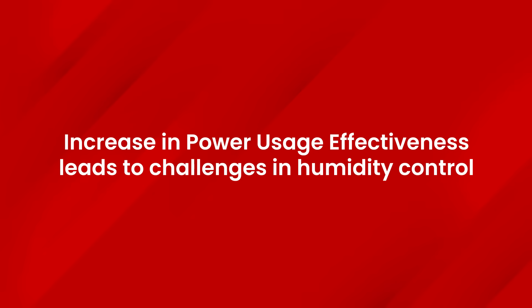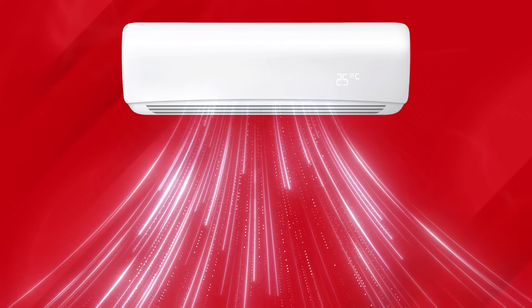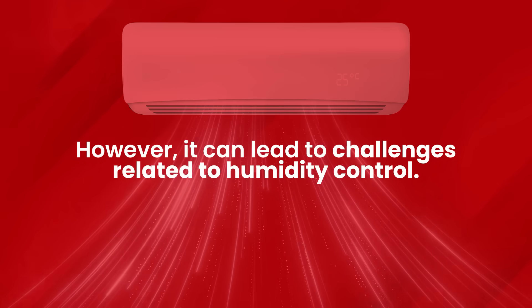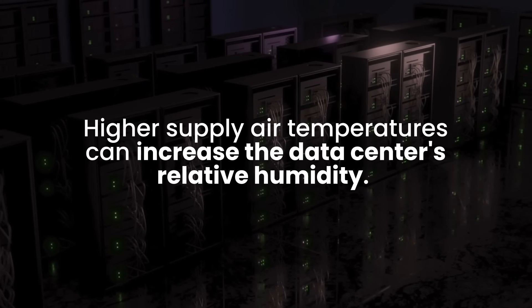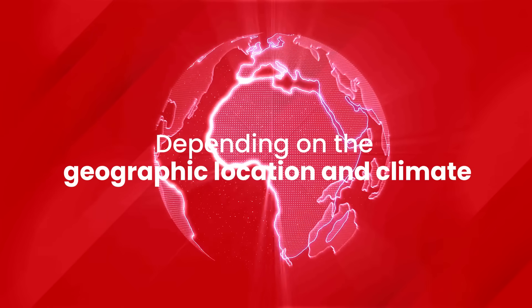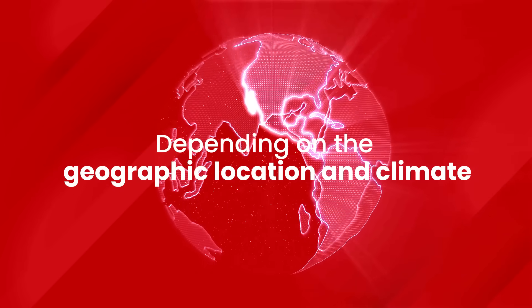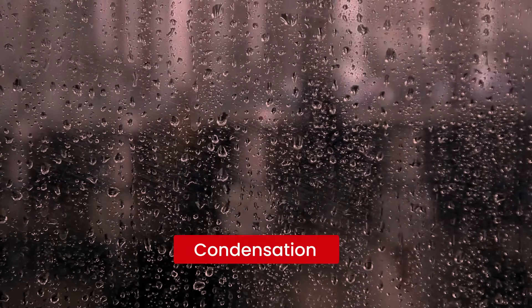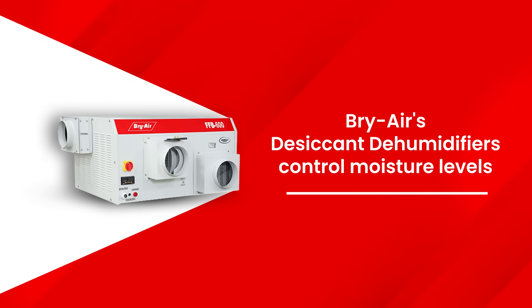To improve power usage effectiveness, data centers have been increasing the supply air temperature. This reduces the need for energy-intensive cooling systems, such as traditional air conditioning. However, it can lead to challenges related to humidity control. Higher supply air temperatures can increase the data center's relative humidity. Depending on the geographic location and climate, this can lead to humidity-related problems — excess humidity can cause issues like condensation, damaging equipment and leading to electrical short circuits. To counter this, Bry-Air's desiccant dehumidifiers control the moisture levels, safeguarding equipment from humidity-induced damage.